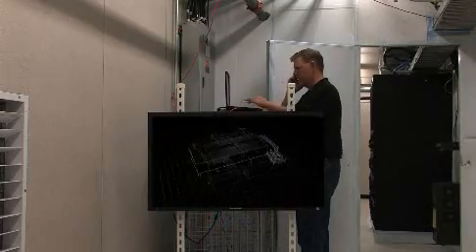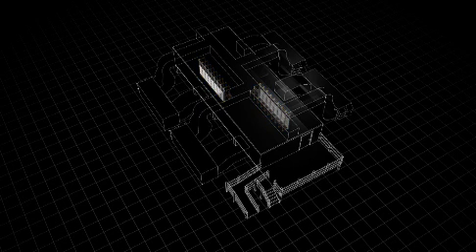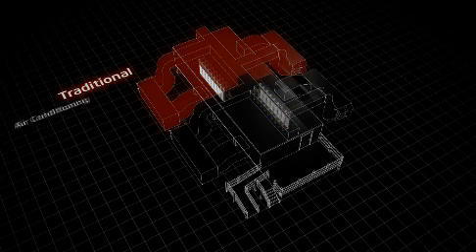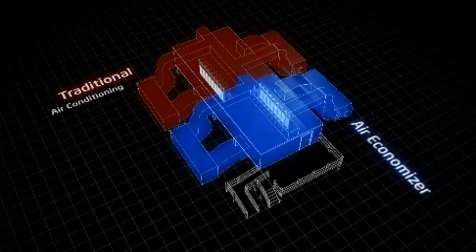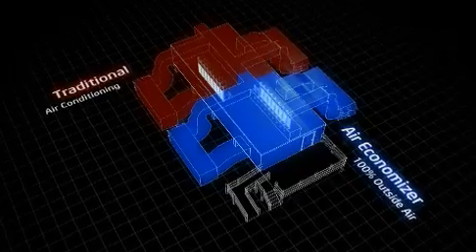Over a 10-month period, we have been running an air economizer test using approximately 900 heavily utilized production servers in a high-density data center. The data center was divided into two sections with an equal number of servers on each side. One side running as a traditional data center with air conditioning, and the other side running the air economizer proof of concept with 100% outside air for cooling.